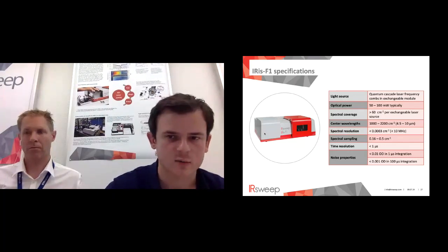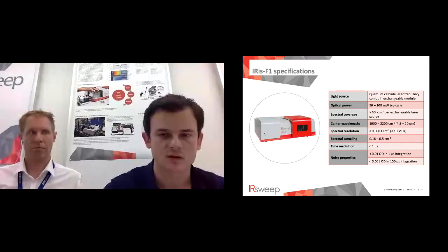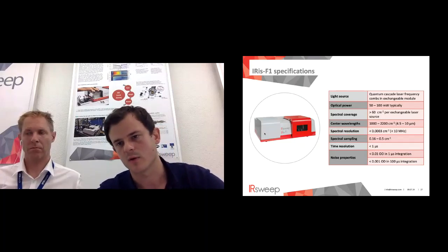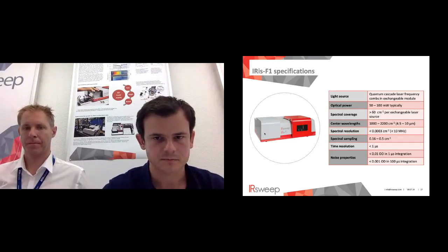I want to mention that when you do exchange the laser source in your system, you don't have to realign the whole system. So when you put in another laser, you switch it on again, you already do see a signal. You may want to maximize it a bit, but that's a matter of 1 or 2 or 5 minutes and not a realignment effort of hours.